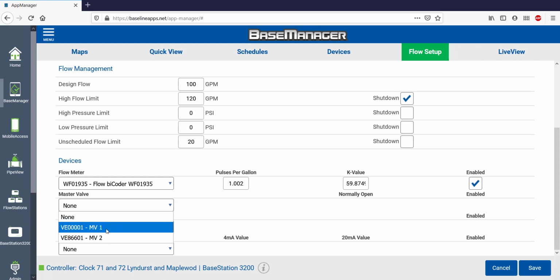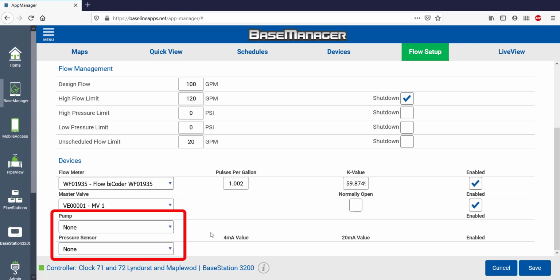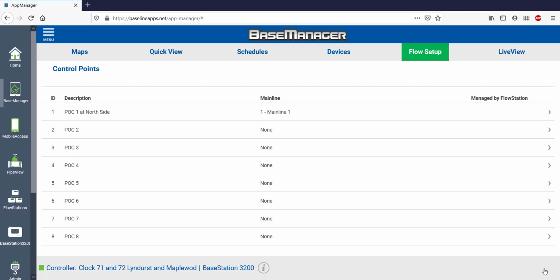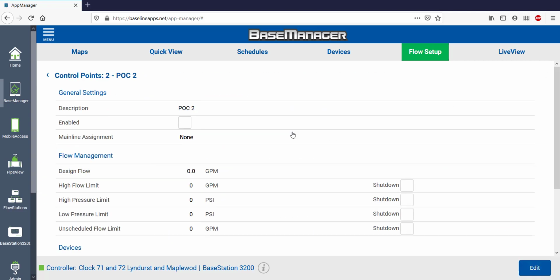My more complex system has 2 master valves in the drop-down menu, so make sure you select the correct one. This first master valve is normally closed, so I'm going to leave the normally open box unchecked. If I had a pump or pressure sensor, I'd be able to select them here. That's all for control point 1, so save it before going on to control point 2.